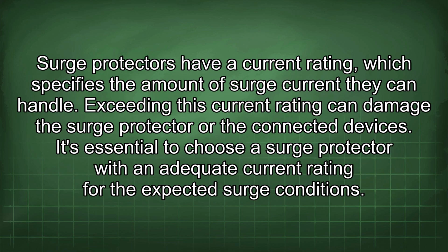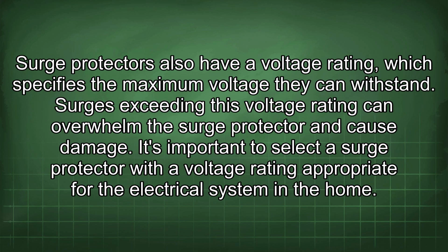Surge protectors have a current rating, which specifies the amount of surge current they can handle. Exceeding this current rating can damage the surge protector or the connected devices. It's essential to choose a surge protector with an adequate current rating for the expected surge conditions. Surge protectors also have a voltage rating which specifies the maximum voltage they can withstand. Surges exceeding this voltage rating can overwhelm the surge protector and cause damage. It's important to select a surge protector with a voltage rating appropriate for the electrical system in the home.